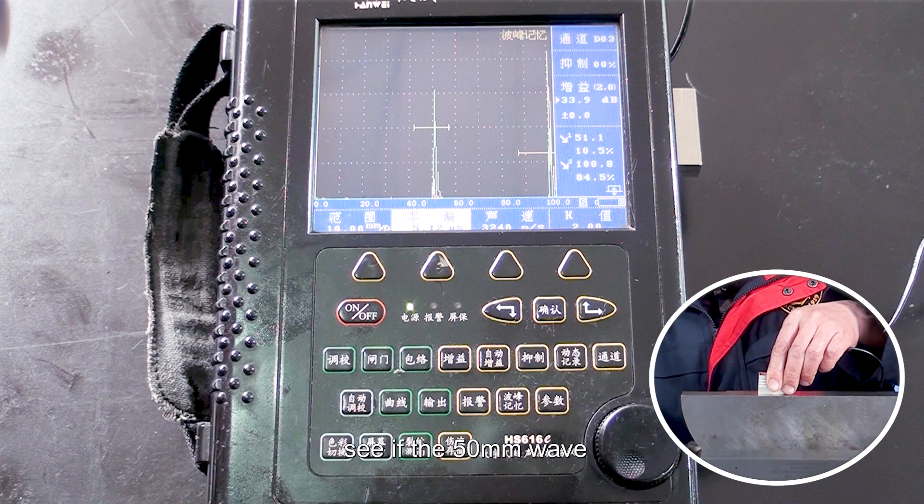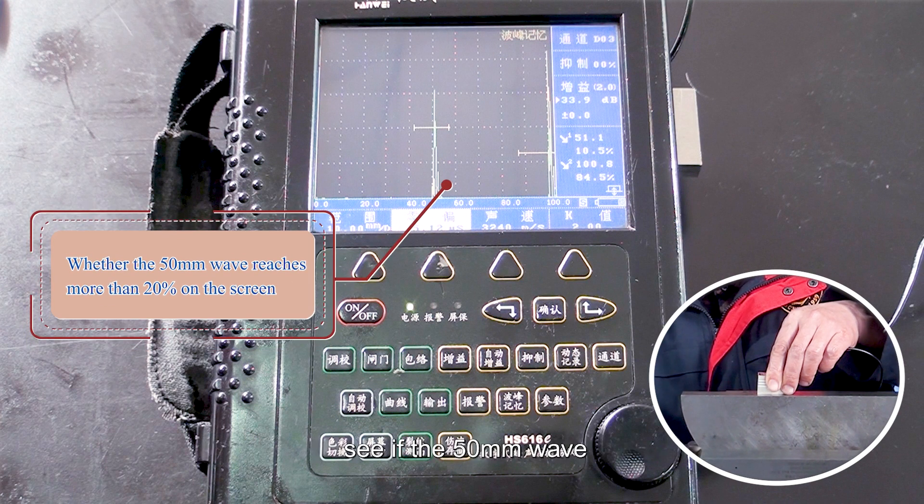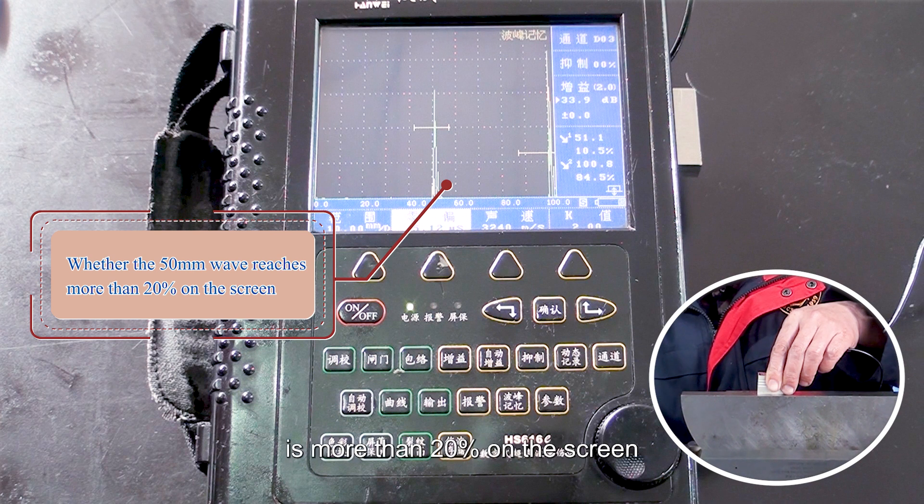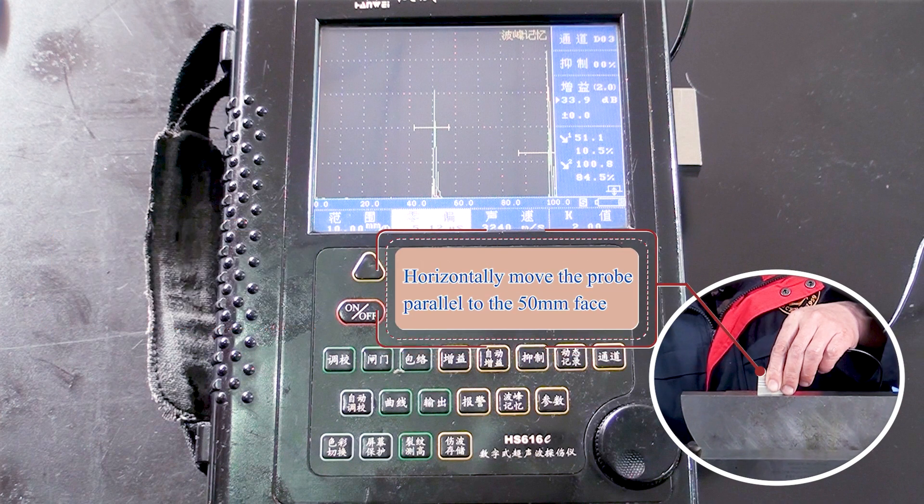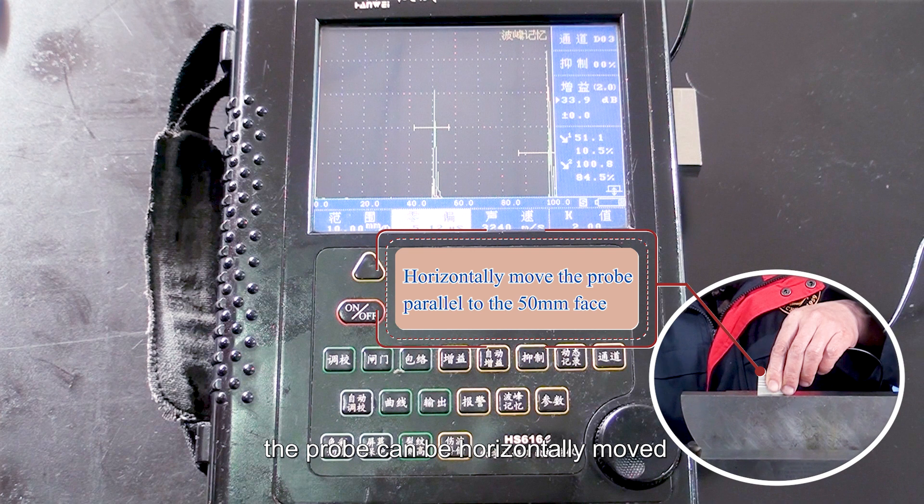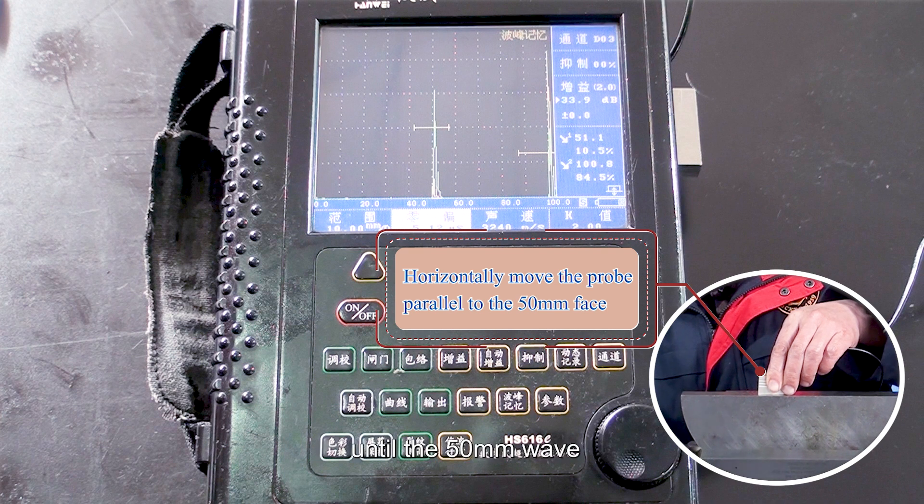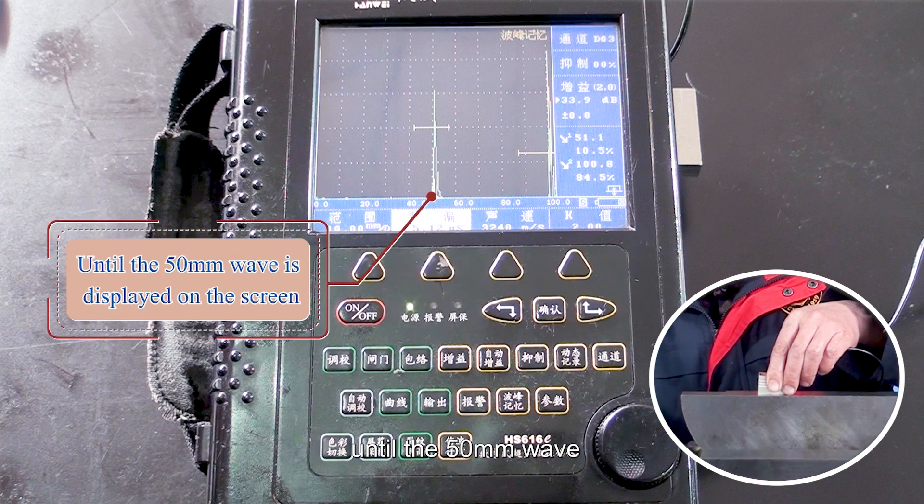At this time, see if the 50 mm wave is more than 20 percent on the screen. If it is lower than that, the probe can be horizontally moved to the 50 mm face in parallel until the 50 mm wave is displayed on the screen.